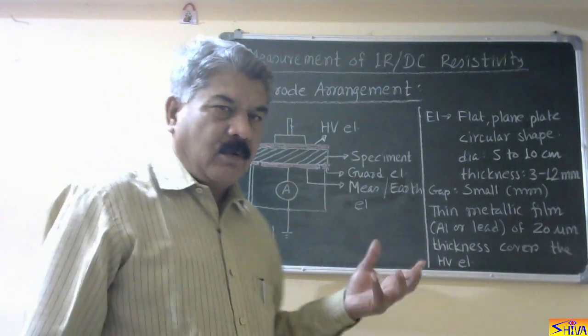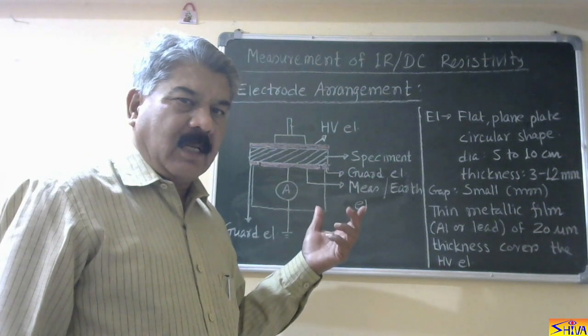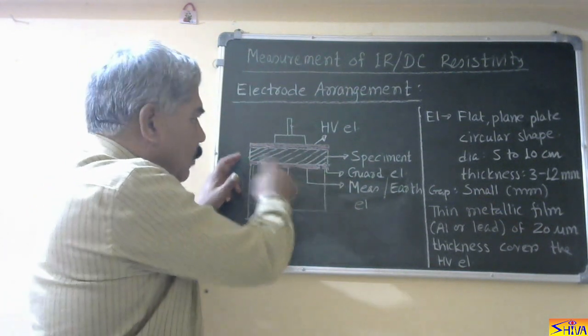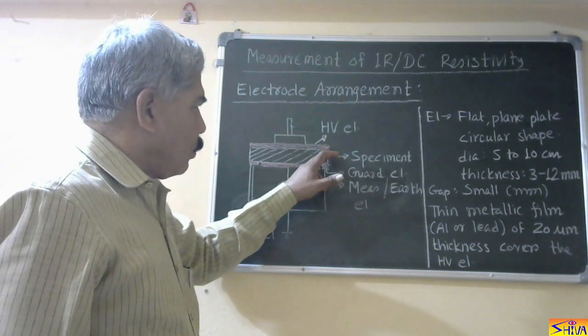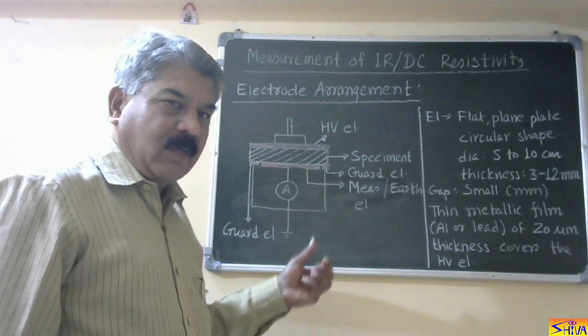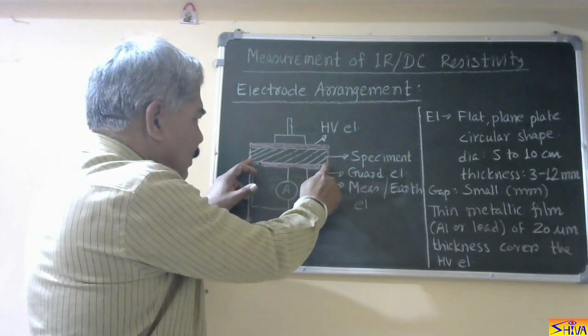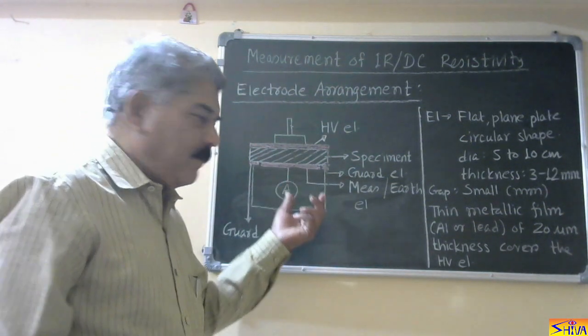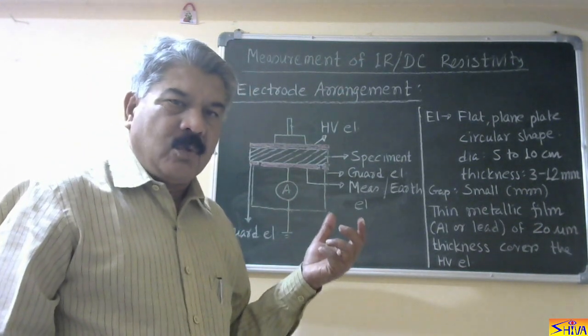Now, why do we require a three-electrode arrangement? Two-electrode arrangement will also serve the purpose, but three-electrode arrangement gives a more precise reading. The reason is we have to measure the current going through the insulation. When we use just two electrodes, current may flow over the edges of the specimen, causing error in reading. Therefore, we use the guard electrode so that whatever current is flowing over the edges is bypassed and not measured. Only the current flowing through the specimen is measured. Therefore, three-electrode arrangement is always better than two-electrode arrangement.